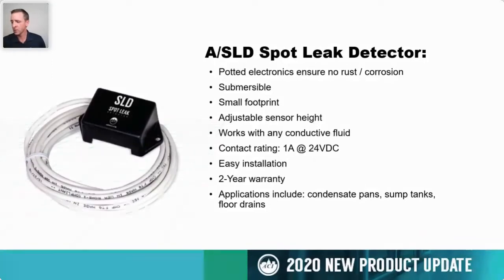One thing I'd like to highlight about this spot leak detector is that these are often used as a fail-safe or a last line of defense to protect critical equipment and critical facilities from flooding or some catastrophic water event that can damage equipment or facilities. This is not the type of product that you want to search for the cheapest option out there, as these are fail-safe devices that can be used to potentially prevent thousands and thousands of dollars of damage. You want to ensure that this product is going to work and going to work when you need it most. Having one fail after a flood or a major leak is not the time that you want to find out that the spot leak detector didn't work.